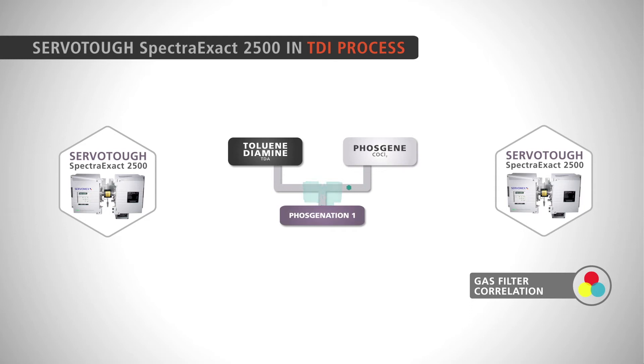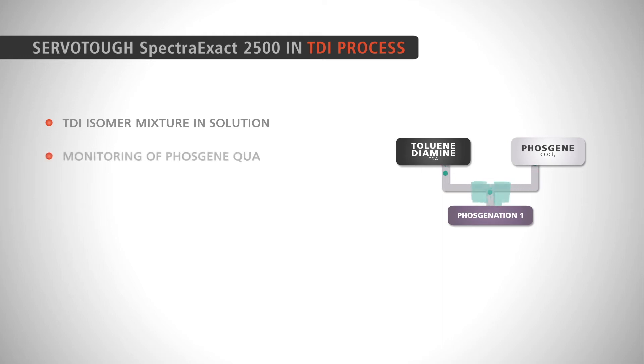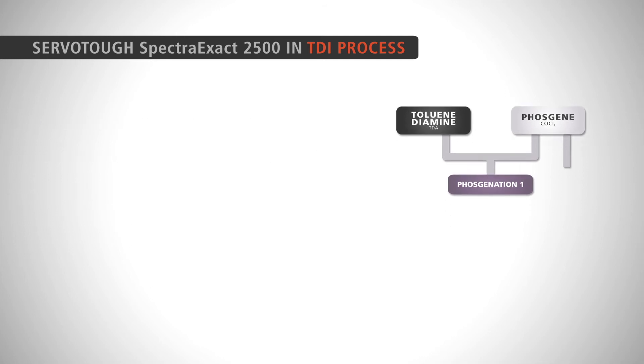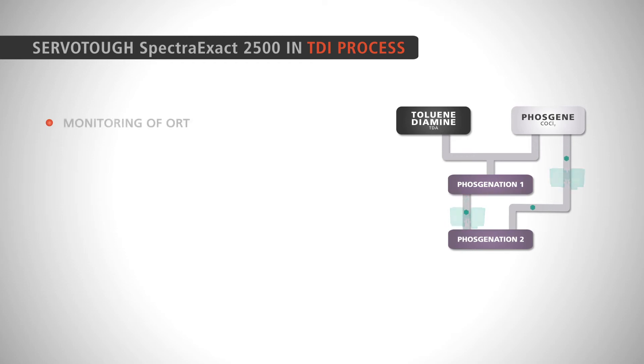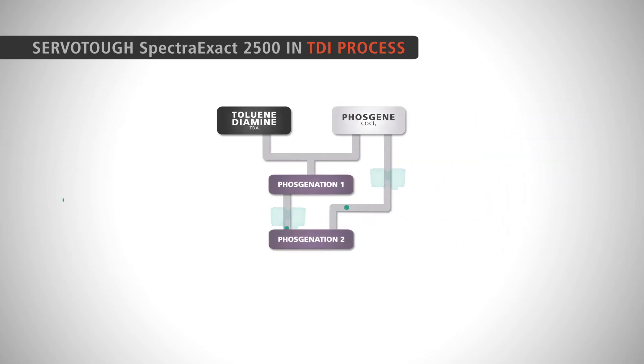This results in a TDI isomer mixture in solution, which then undergoes the phosgenation process. The Spectra Exact 2500 closely monitors phosgene quality and purity, as well as impurities including hydrogen chloride, carbon monoxide, and moisture. It also monitors the ortho-dichlorobenzene byproduct for water and isocyanate groups, which are liquid-phase measurements.